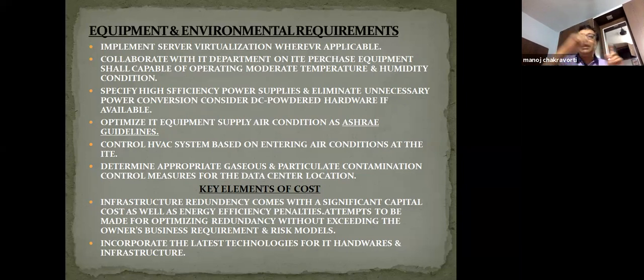Why I am saying that inbuilt systems in some cases are very effective is because these inbuilt systems on the racks automatically switch off the AC as soon as the bank of racks stops operating. And when the racks start again, that system automatically starts. Otherwise you will have to control that load, so that whenever your load is going down you switch off or your part load operation starts, and whenever load is going up, your part load operation is on. So that problem will be over.